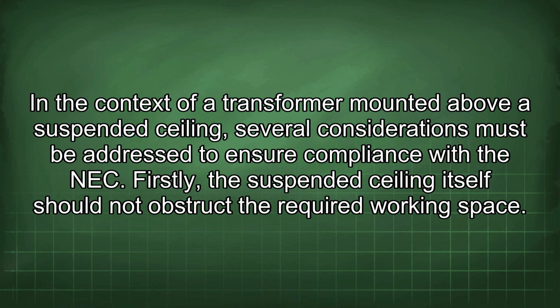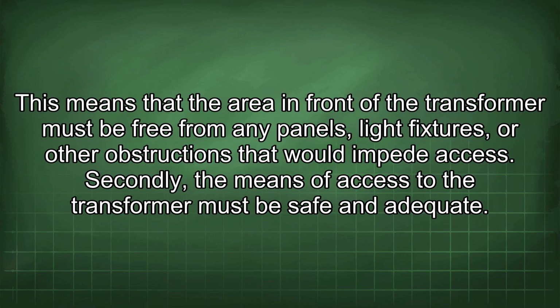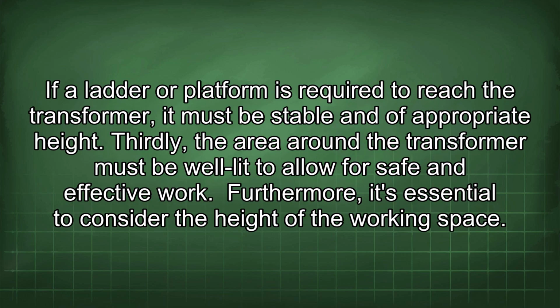In the context of a transformer mounted above a suspended ceiling, several considerations must be addressed to ensure compliance with the NEC. Firstly, the suspended ceiling itself should not obstruct the required working space. This means that the area in front of the transformer must be free from any panels, light fixtures, or other obstructions that would impede access. Secondly, the means of access to the transformer must be safe and adequate. If a ladder or platform is required to reach the transformer, it must be stable and of appropriate height. Thirdly, the area around the transformer must be well lit to allow for safe and effective work.